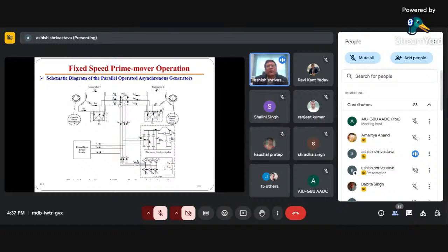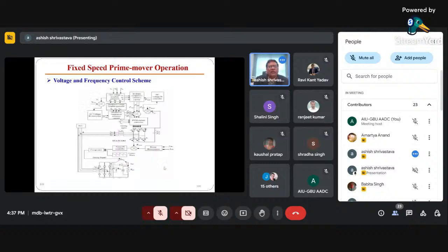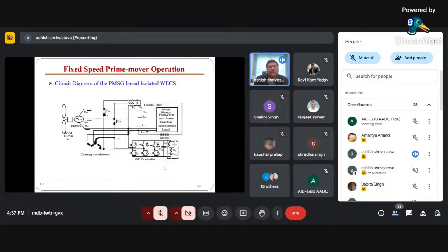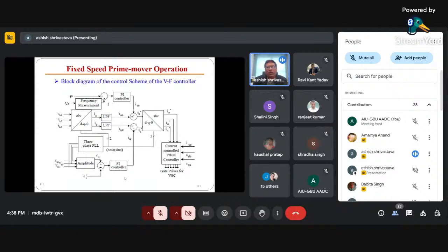Then this is the parallel operated asynchronous generator. If you operate two in parallel, that can also be done. Then this is another scheme of static compensator, using the static compensator for voltage and frequency control. This is with PMSG; the earlier one was with the induction generator. The same thing can be done with a permanent magnet synchronous generator as well. So here, this is a zigzag transformer, and this is a voltage frequency controller, whose control scheme takes care of the PWM pulses as per voltage frequency control. This is the block diagram for generating the voltage frequency control.